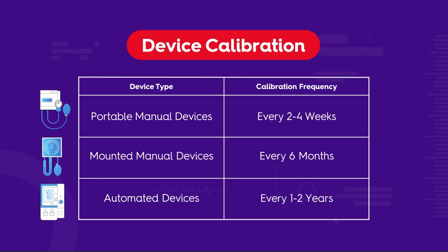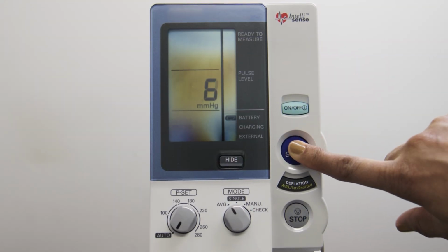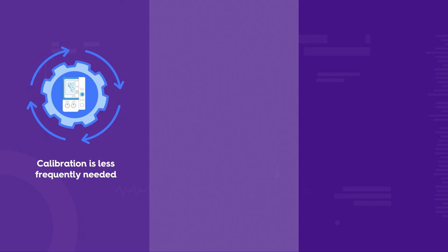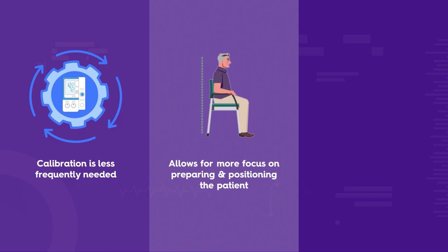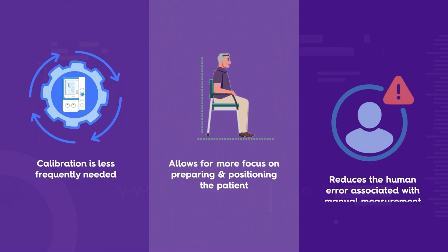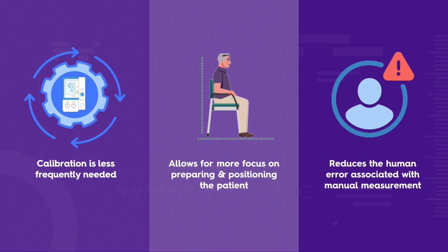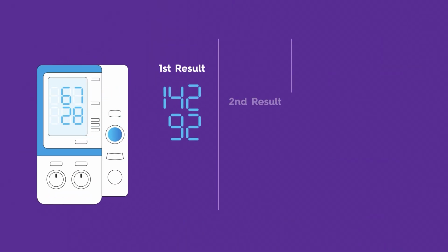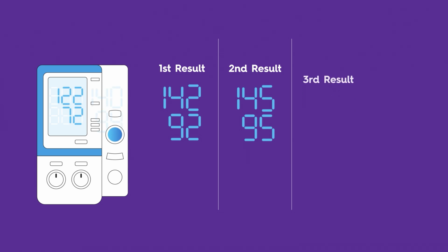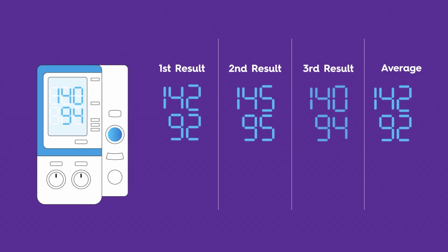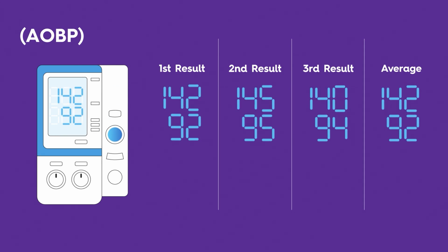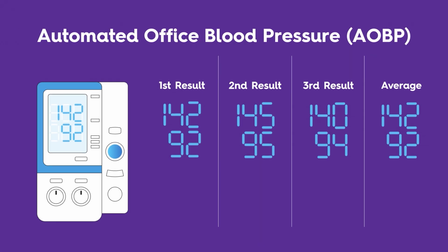Blood pressure devices can be manual or automated. Automated devices take measurements with the push of a button. With these devices, calibration is less frequently needed. The person taking the measurement is able to focus on preparation and positioning, and the human error associated with measurements may be reduced. Certain types of automated devices can be programmed to take multiple blood pressure measurements and average the results with a single activation or push of a button. These devices are called Automated Office Blood Pressure, or AOBP.